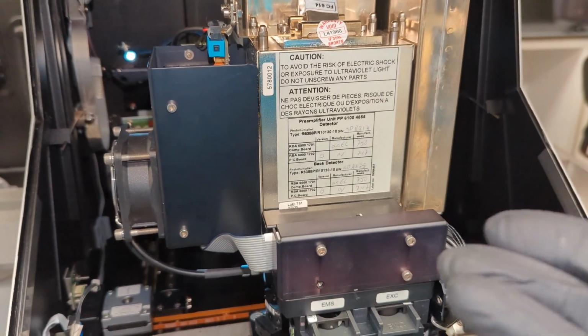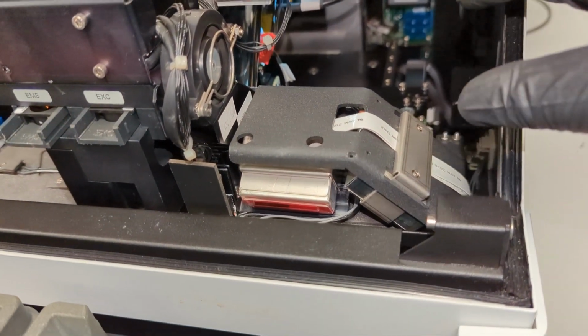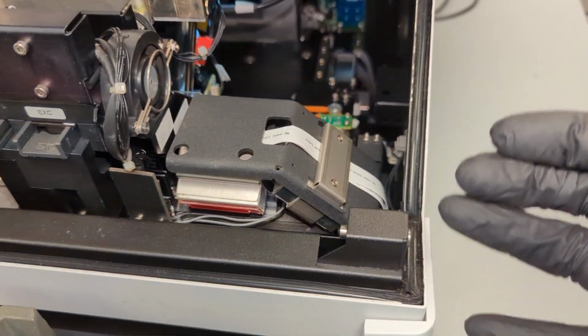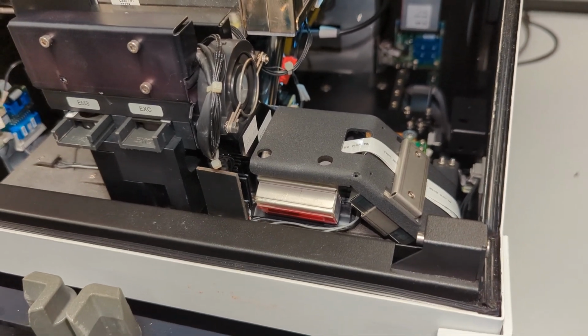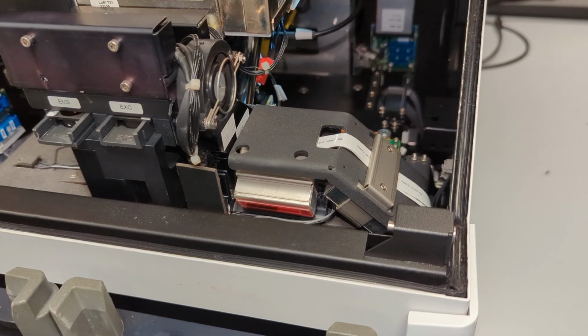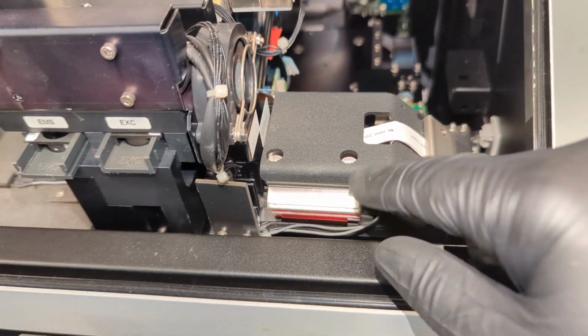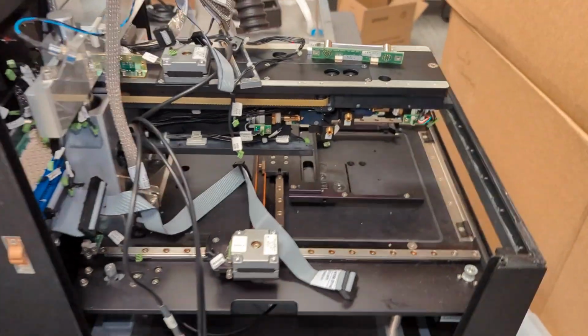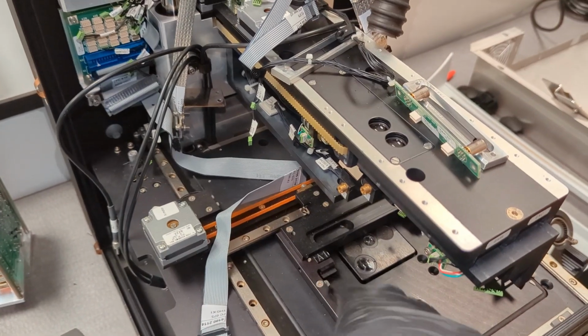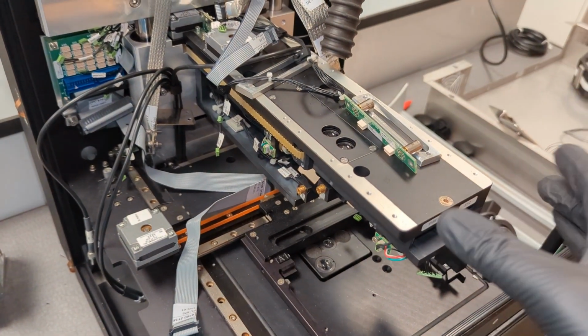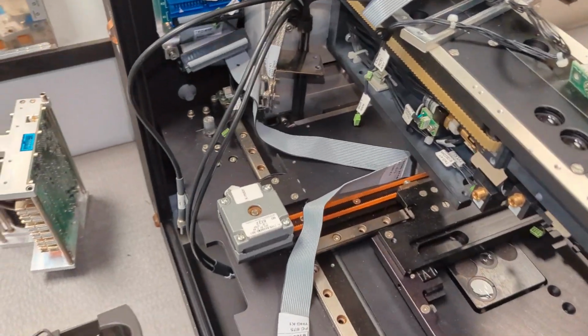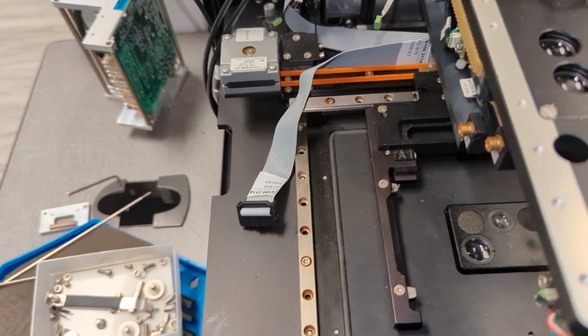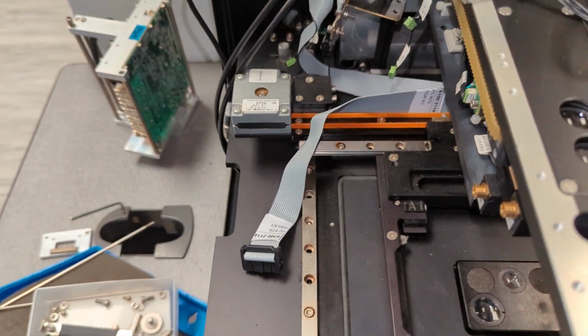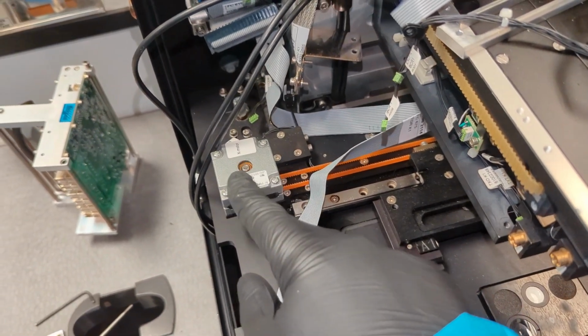All right, now I think now would be a good time maybe to take a look at the inside of one of these PMTs. But real quick, this instrument also has some barcode readers so that you can actually read barcoded plates, and that might be more so for heavily regulated environments, or if you're doing high throughput screens where you barcoded your plates. That is what this assembly is for right here. All right, and of course you need a way to move the plate around so that it can do each of the wells, because the measuring head isn't moving anywhere. It's moving up and down, but it's not moving in the X and Y. And so that is done... your plate would sit here, and it's being moved in the X and Y on these linear ball bearing rails. And there's also an X motor.